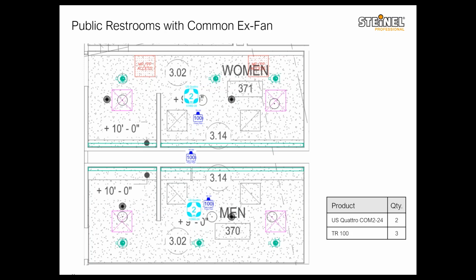So as you can see, we have the US Quattro COM2-24 in each of the restroom areas, one power pack for lighting control in each of them, and one power pack that will be controlled by both of the occupancy sensors for the common exhaust fan. I'm saying it will be controlled by both of them, but a signal from either of them will turn the exhaust fan on, obviously. So you don't need both restrooms to be occupied for the exhaust fan to work.